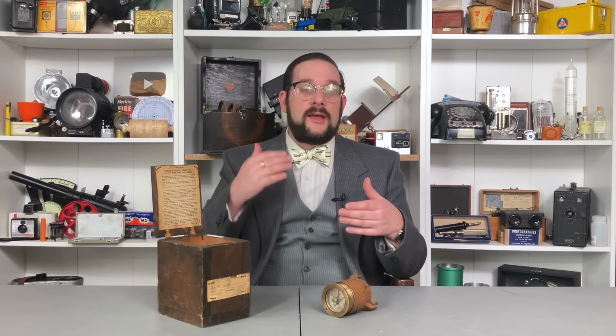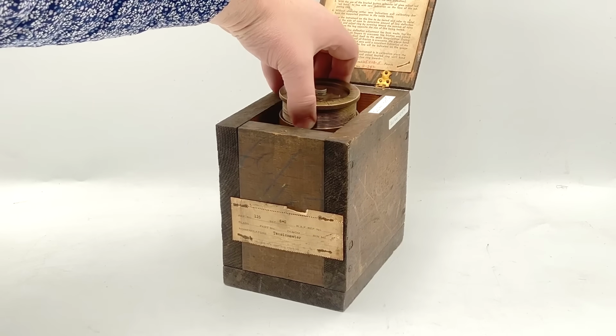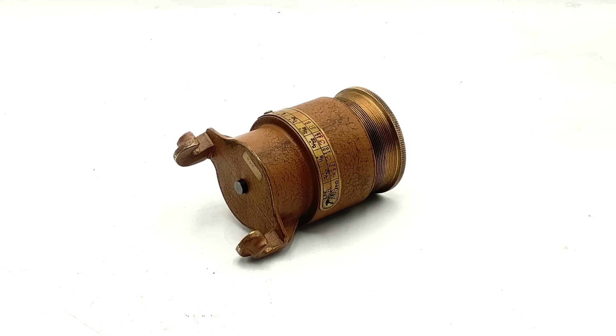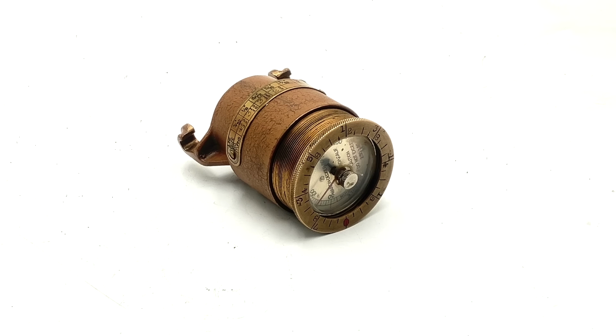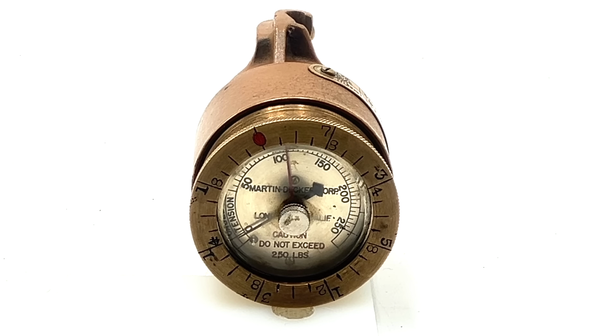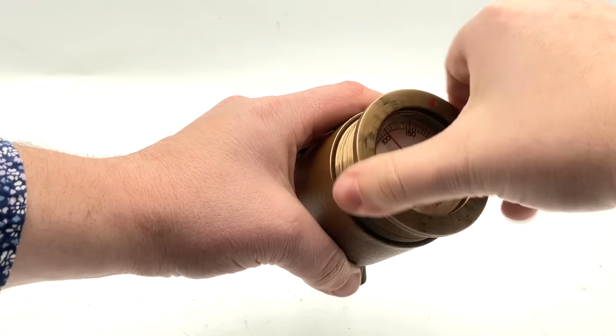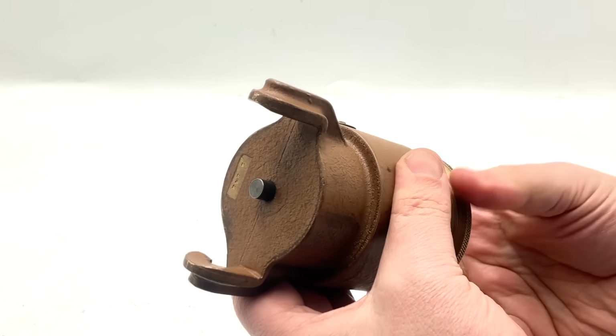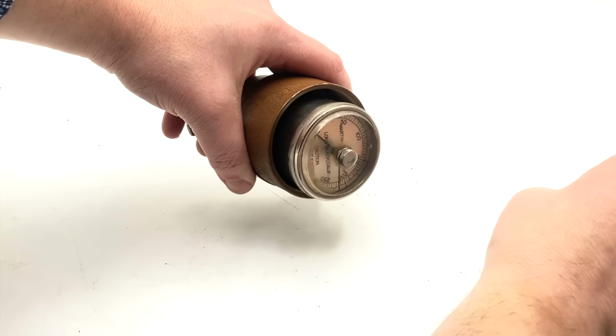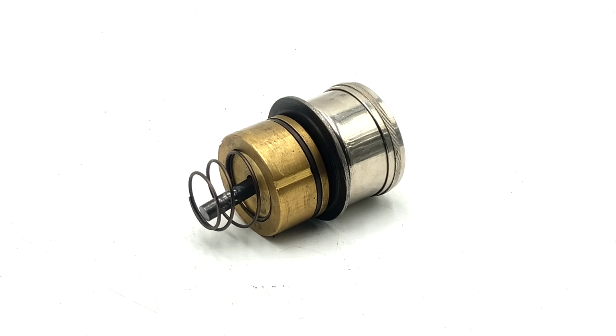Right, so if we pull the unit out of its box, we can see that at one end we have a pair of hooks for holding the cable being measured and a retractable piston for applying transverse force to said cable. While at the other end, we have a readout dial calibrated in pounds force and a threaded housing that can be rotated to extend or retract the piston and vary the force applied to the cable. If we unthread this, we can see that the gauge itself is a sealed unit. The piston presses on a flexible diaphragm which transfers pressure via hydraulic fluid to the gauge.